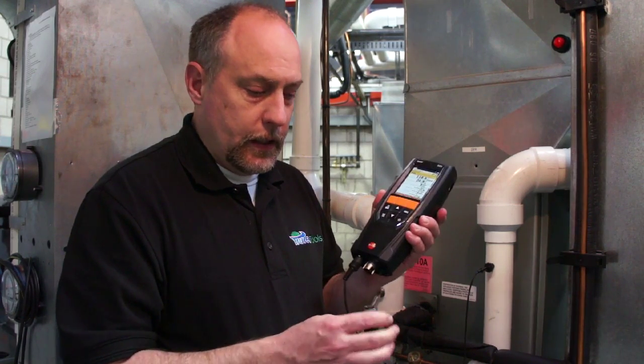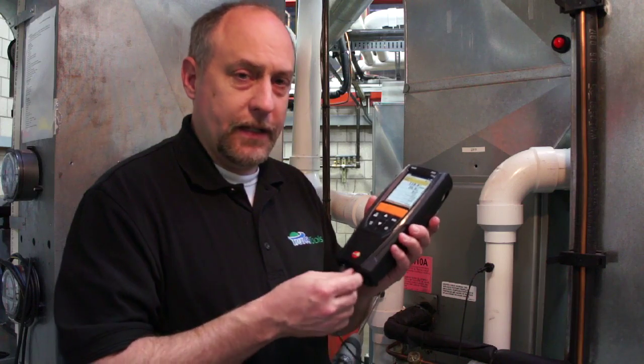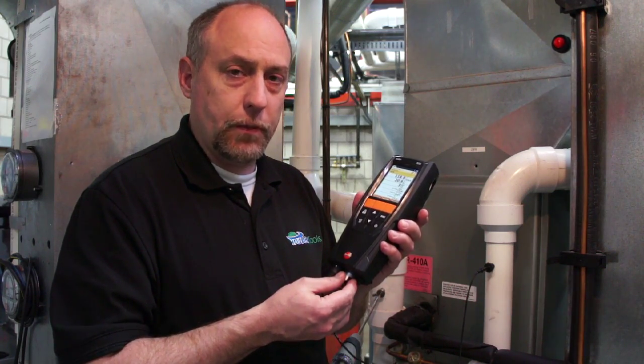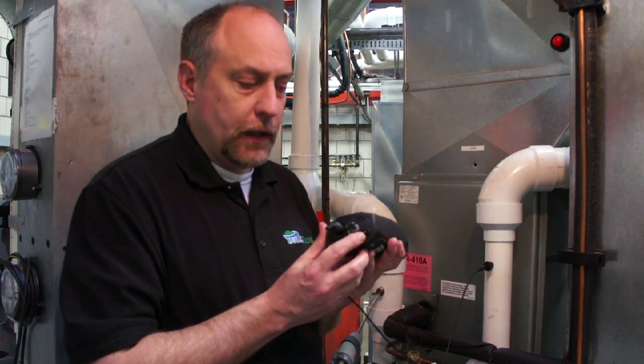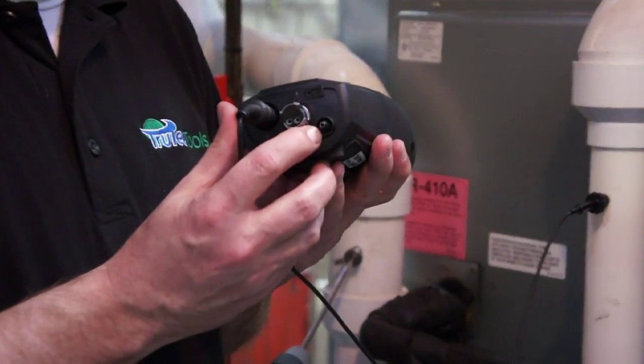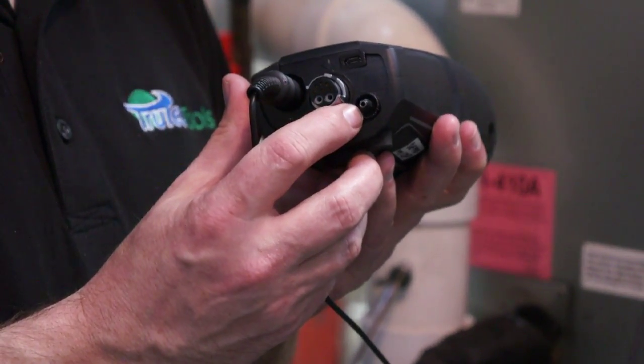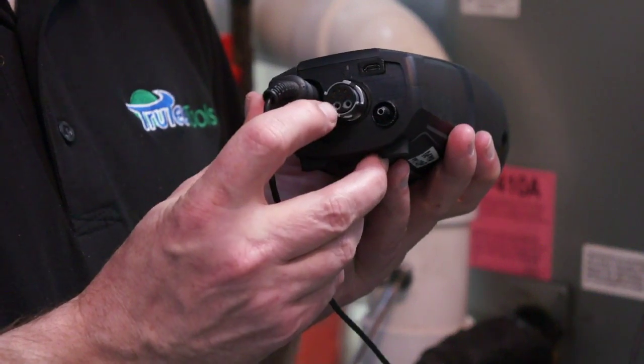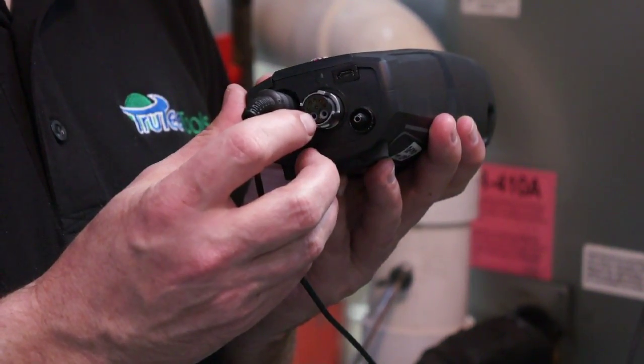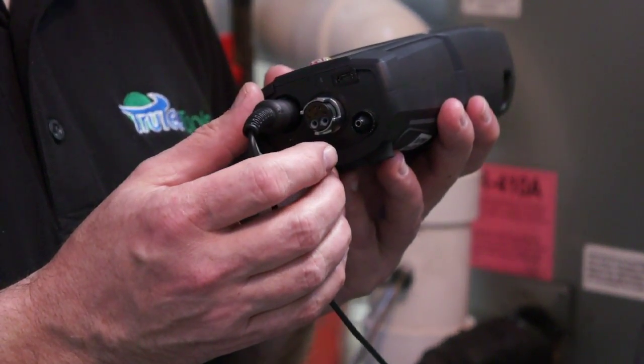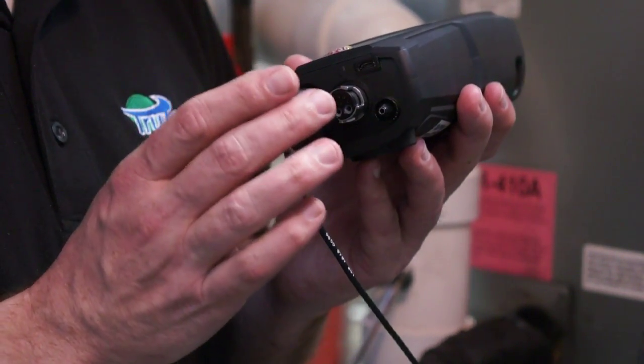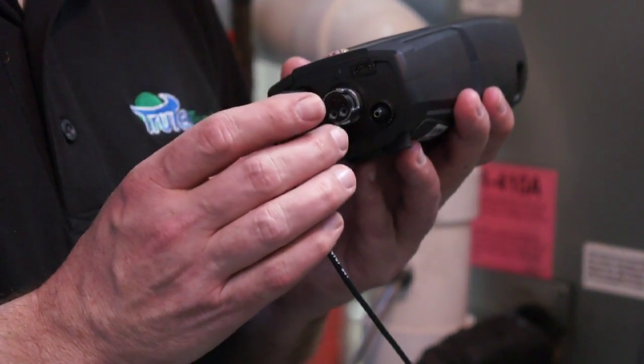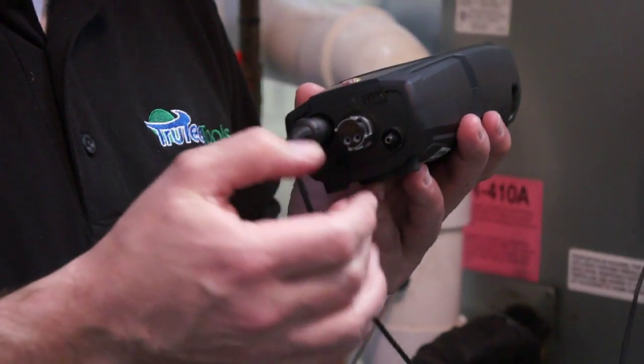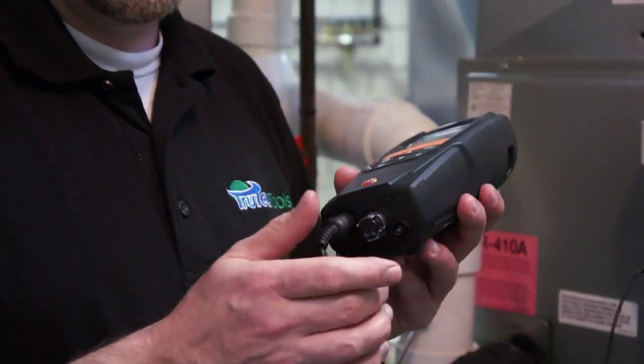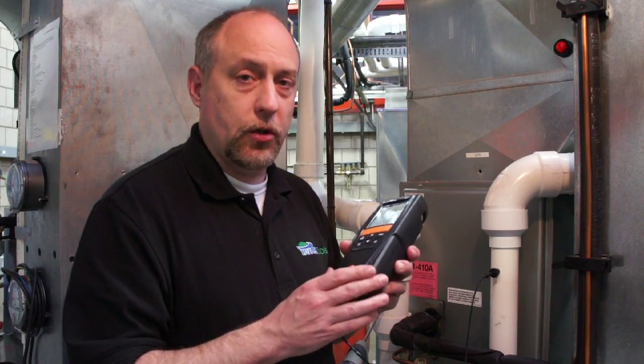Also, you can unplug the flue gas probe and plug into the bottom of this a differential pressure port. The 320 does have differential pressure, so you can see there's a differential pressure port on the bottom of the instrument. This is the negative side, or this is the positive side of the differential pressure port. The negative side's built in here, and you do want to make sure that you use the accessory. Don't just slide a hose over top of the probe assembly to measure pressure, because if you do that, you're going to pressurize the flue gas path and the manometer port. You don't want to do that. The accessory probe that snaps on here isolates off the flue gas path so that we only pressurize the pressure transducer and we don't take a chance at making an internal leak inside the instrument.